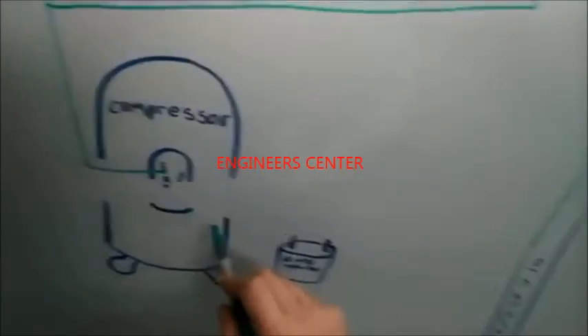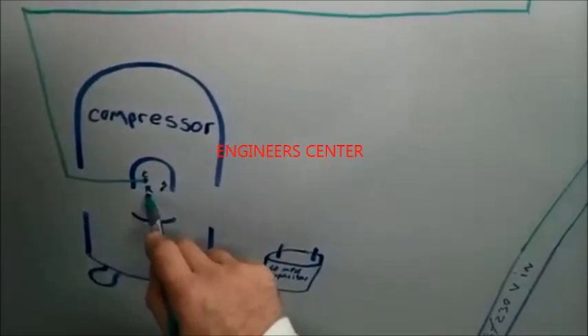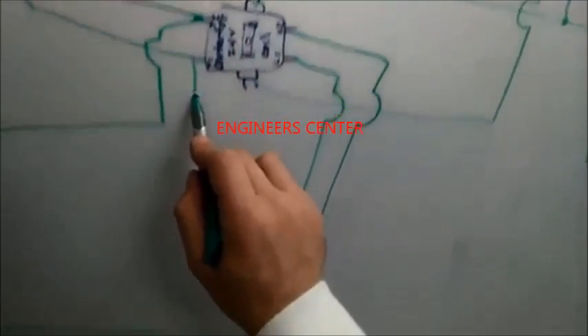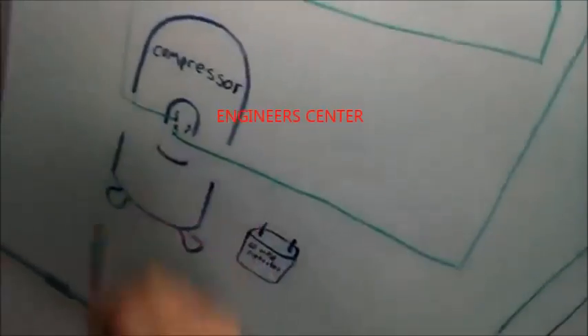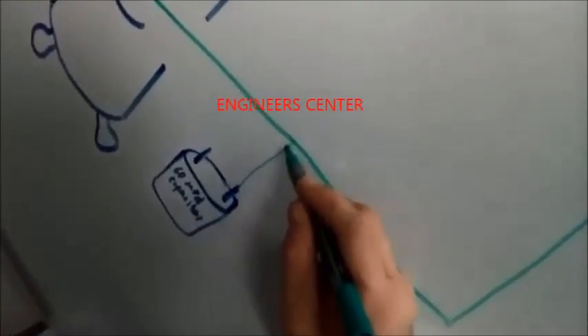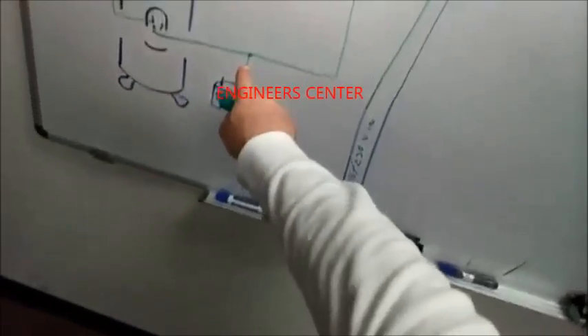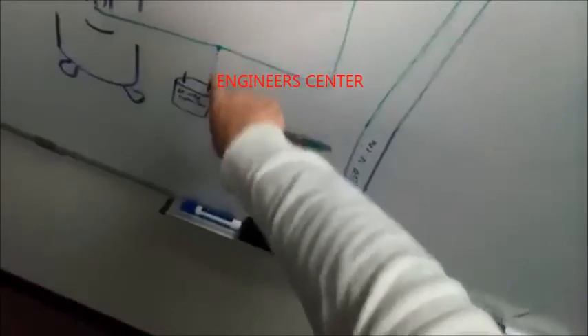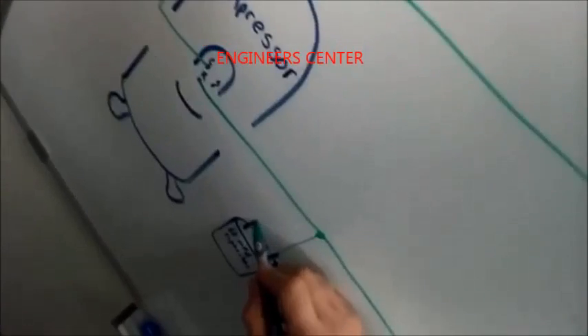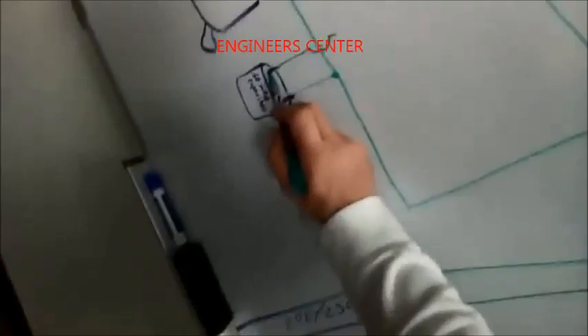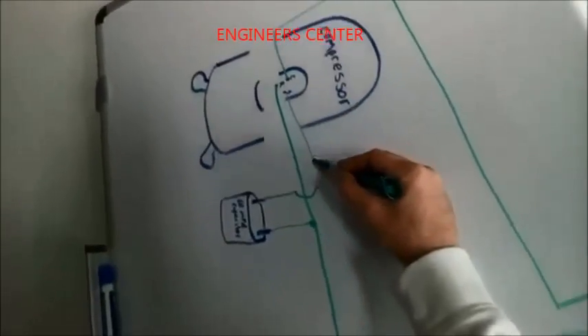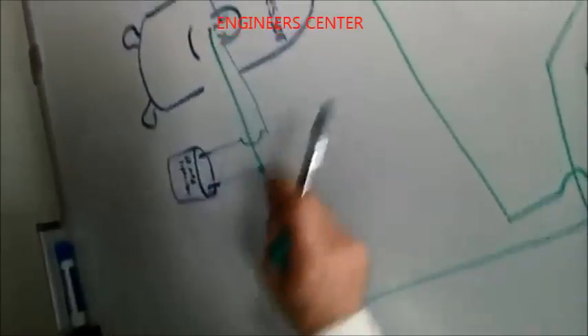Now it also wants the other side of power, but it wants to share that through the capacitor. So run also is the other side of power. But now run also needs to run with a capacitor. So just tie it off. Pretty simple. Now don't get tied up on where this connects, because you could have taken this over and connected it there. It wouldn't matter. We want to bring start from the compressor over here and give it the other side of the capacitor by itself. And there we go.